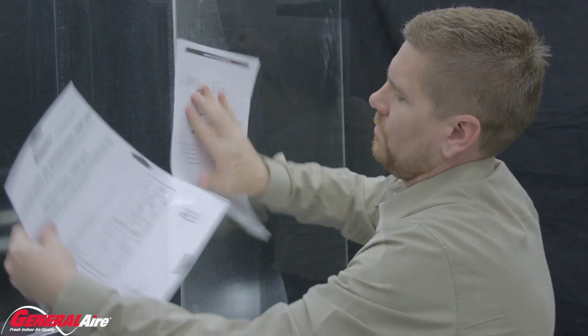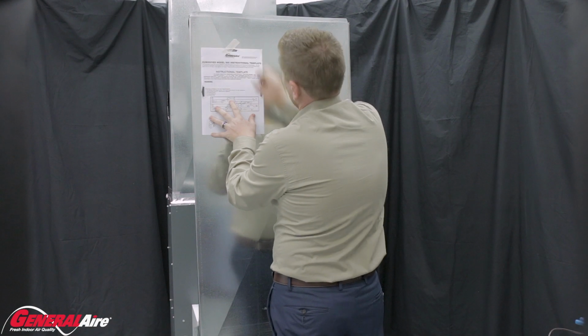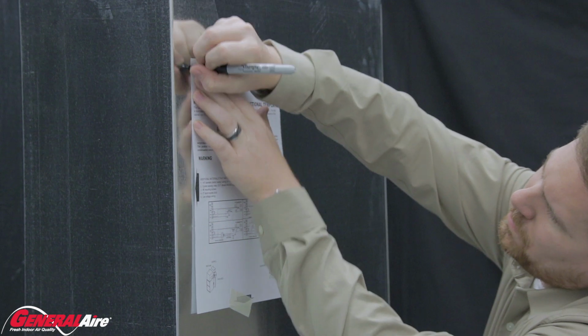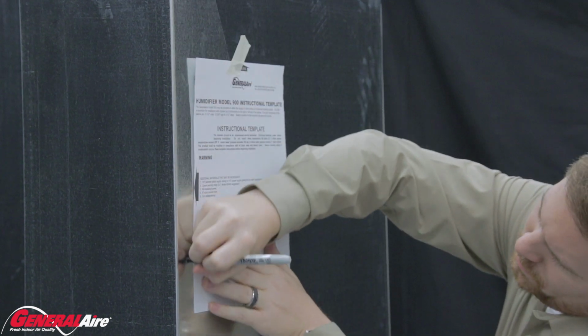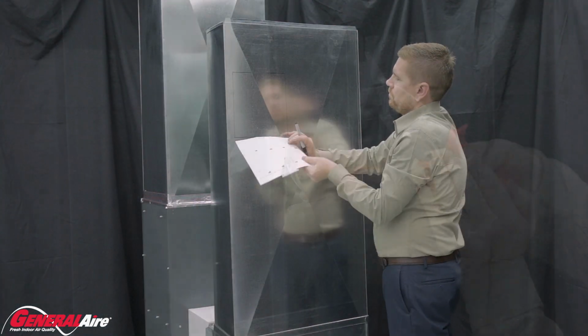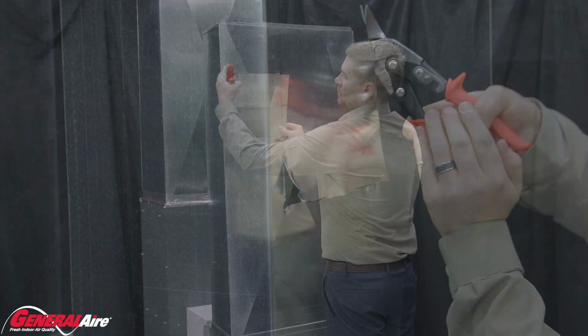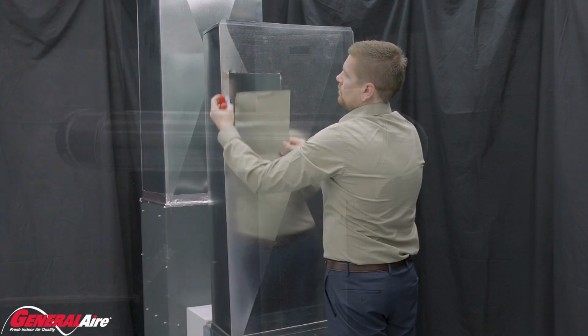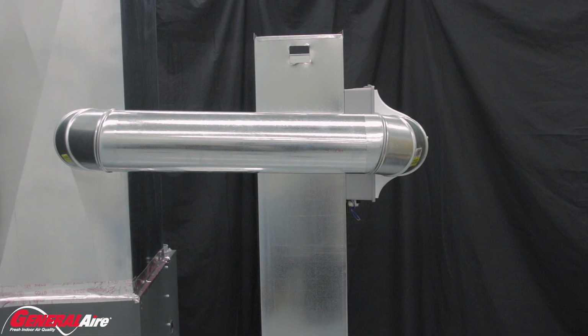First, tear off the template and tape it to the plenum, ensuring it is level. Take a magic marker and draw an outline around the template. Remove the template and, using your tin snips, cut the sheet metal along the lines. Next, we will install the bypass, a round piece of pipe that comes from the side of the 900M, connecting to the ductwork on the return. If you mount your unit on the supply, your bypass goes to your return or vice versa.